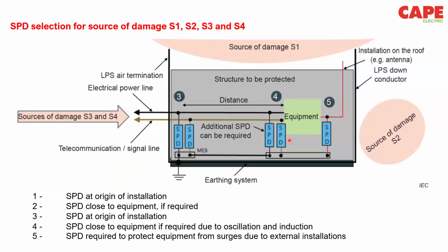How do we select an SPD based on the sources of damage? So for example, for lightning, we have 4 sources of damage. One is direct lightning strike to the building. You can see here, there is source of damage S1. That means direct lightning strike to the building. S2 means lightning strike to nearby the building. So you know that there will be a GPR increase inside the building, and there can be a surge current flowing through it. And then lightning strike to the power line and to the nearby of the power line. So source of damage S3 and S4. So for this condition, for example, how do we define S1, S2, S3, and S4? Basically with the risk assessment. So risk assessment will say whether you have a chance of direct lightning strike to your building, or if there is not a direct lightning strike, but you have more probability of S3 and S4.